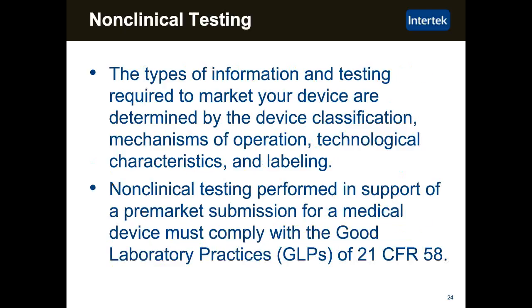Let's talk a little bit about non-clinical testing. So the types of information and testing that are going to be required to market your device are determined by the device classification, the mechanisms of operation, the technical characteristics of the product, and the labeling, and that covers your manuals, your warning labels, and any descriptions of intended use and indications for use. So you'll need to, with your non-clinical or preclinical testing, support all of those claims that you're making on the device.